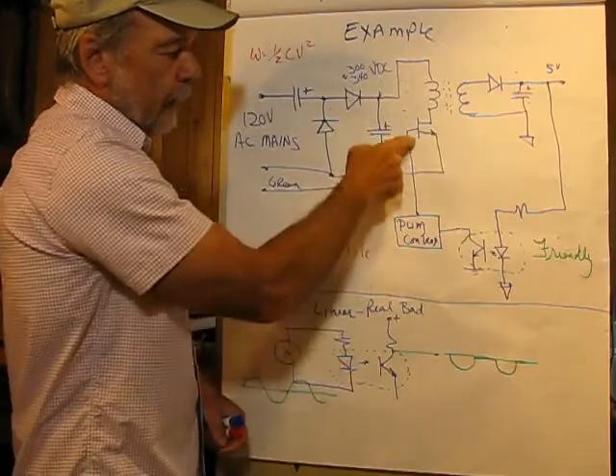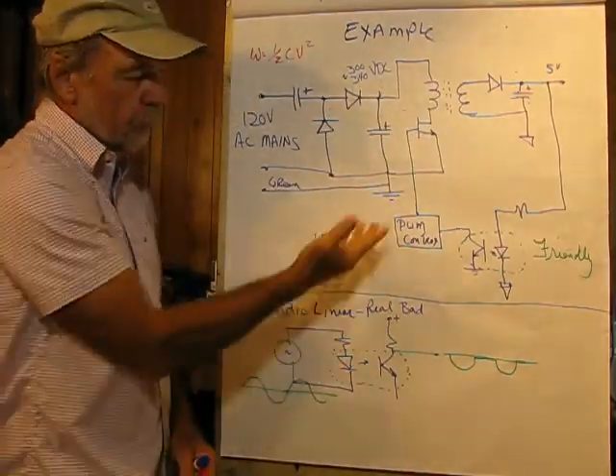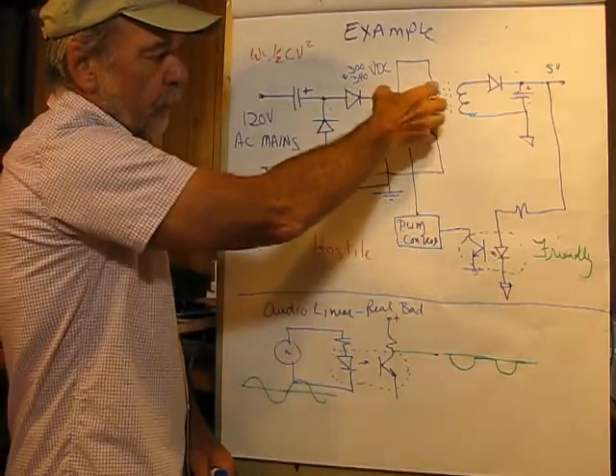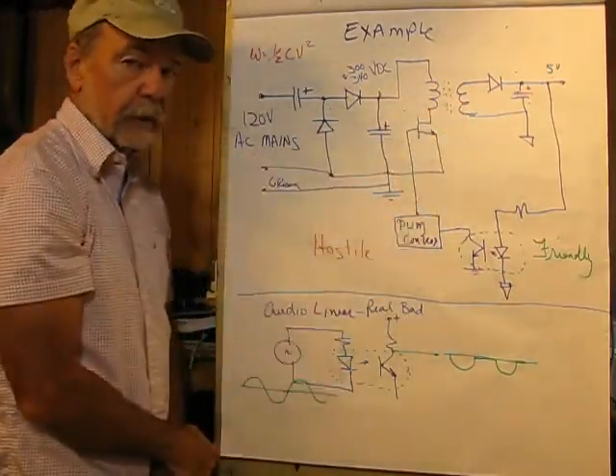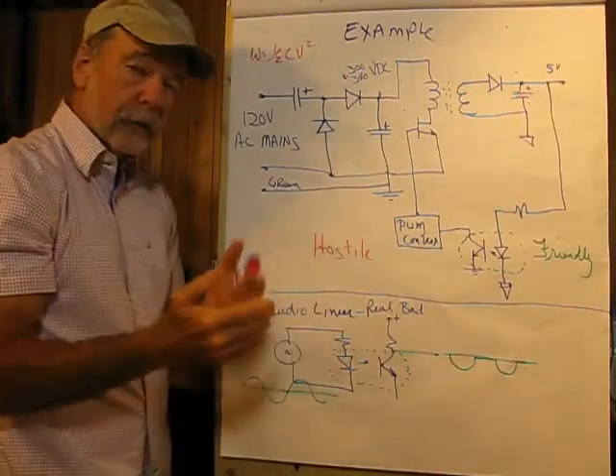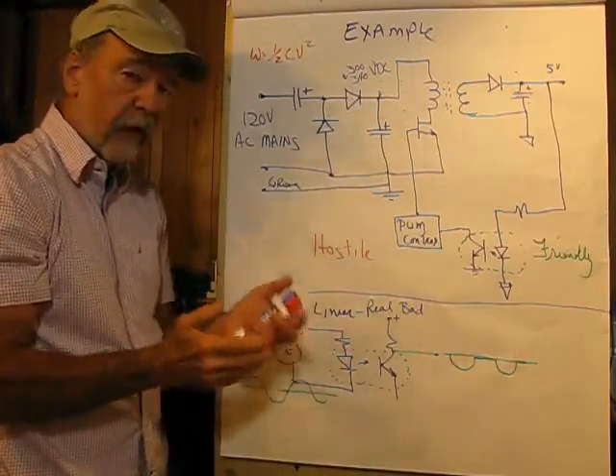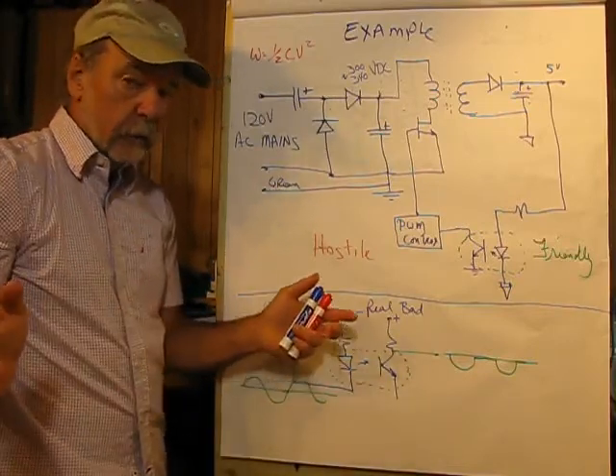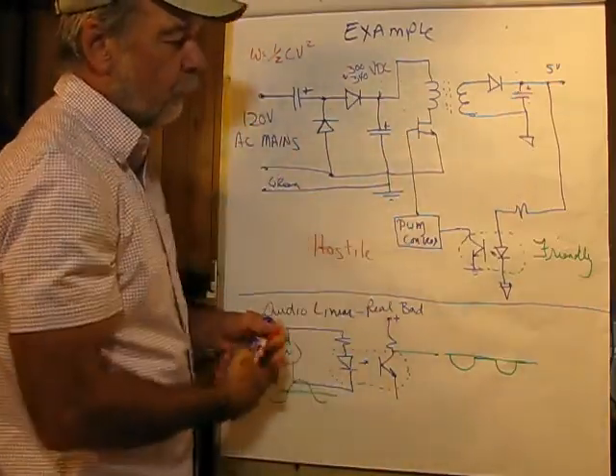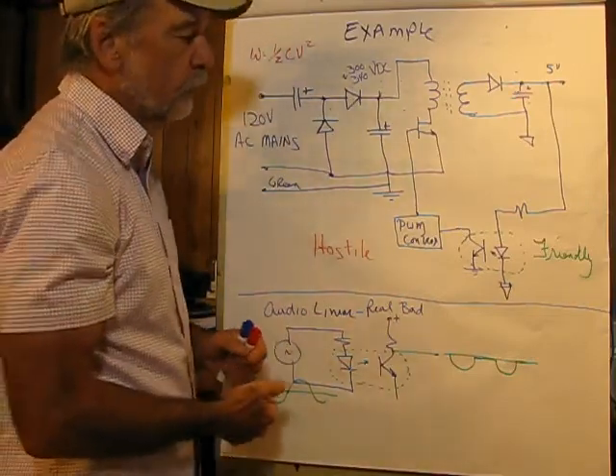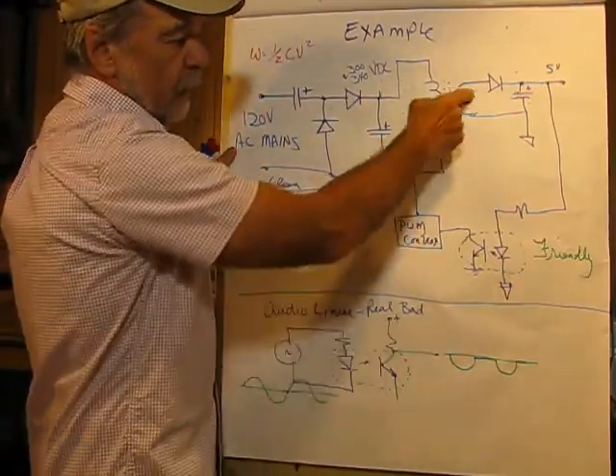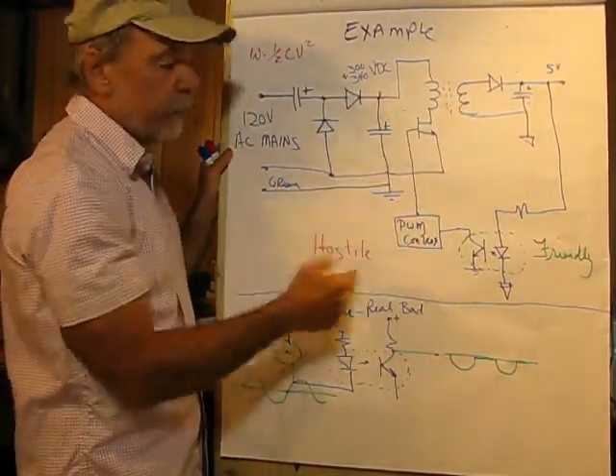And techs used to repair this and a voltage comes into this 120 volt and that's called the AC mains with an S on it and that's the language and because if you flip the power switch on this you take out a whole bunch of fiber optic channels switches on the back okay so what we have here is a voltage doubler so at this point we're talking about 300 to 340 volts DC keeping in mind the peak of this that's a lot and it's sitting on this filter capacitor and the energy of a filter capacitor is equal to one half cv squared so that squared is significant and can have enough energy to really hurt you not kill you if you get across it like you know both hands were going to close across your heart cavity this is fed into a high frequency transformer and I've shown this is not a solid iron core but a ferrite core.